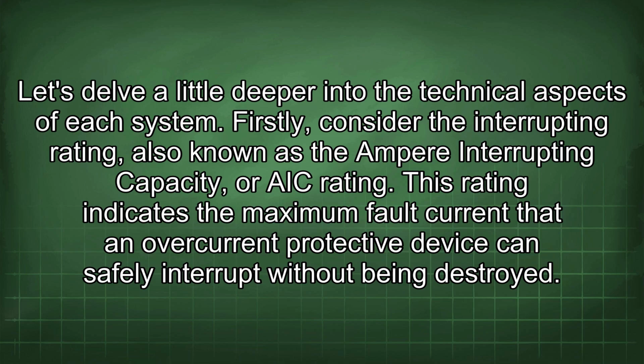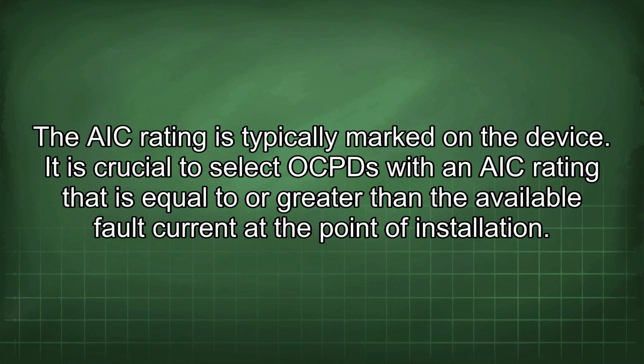Firstly, consider the interrupting rating, also known as the ampere interrupting capacity, or AIC rating. This rating indicates the maximum fault current that an overcurrent protective device can safely interrupt without being destroyed. The AIC rating is typically marked on the device. It is crucial to select OCPDs with an AIC rating that is equal to or greater than the available fault current at the point of installation.